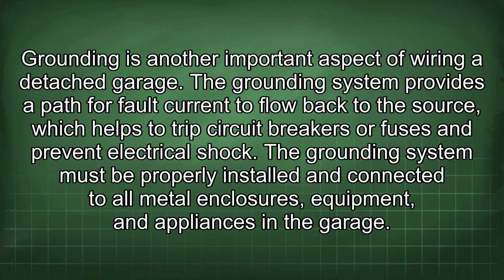Grounding is another important aspect of wiring a detached garage. The grounding system provides a path for fault current to flow back to the source, which helps to trip circuit breakers or fuses and prevent electrical shock. The grounding system must be properly installed and connected to all metal enclosures, equipment, and appliances in the garage.